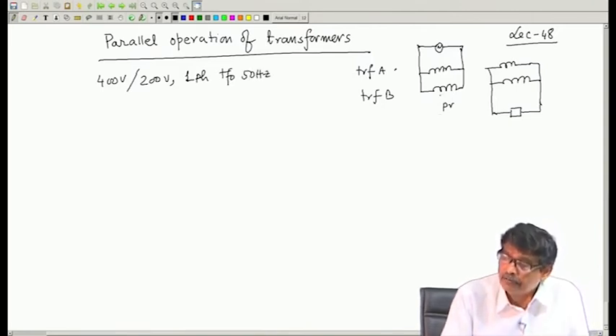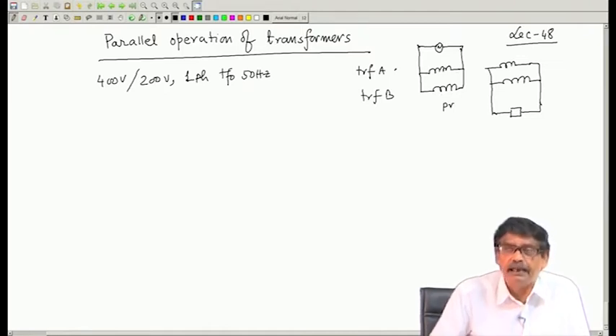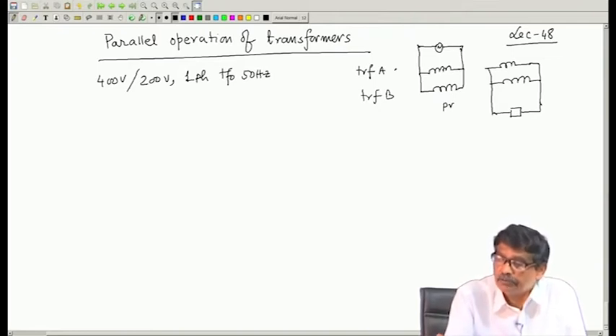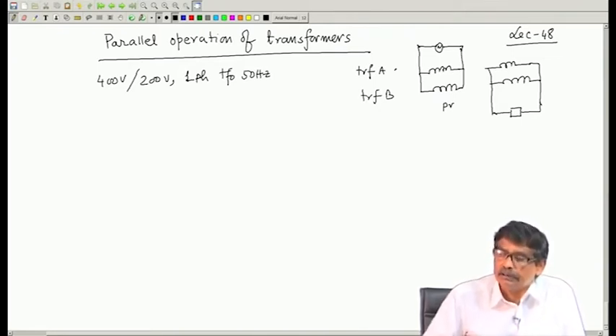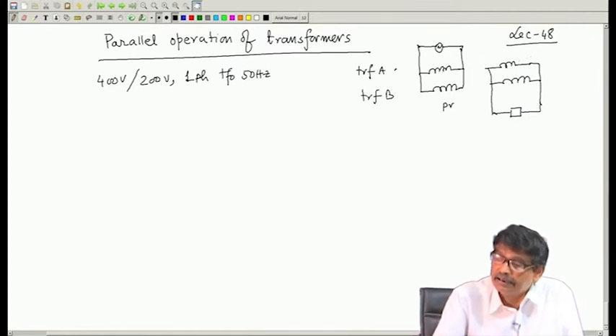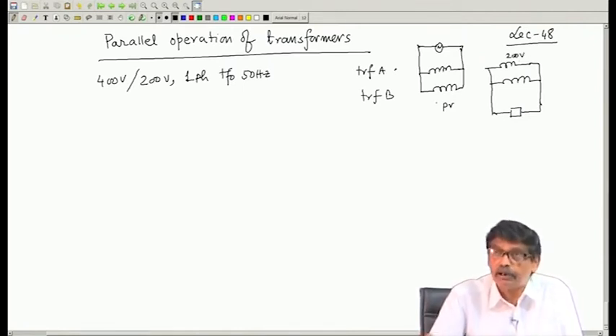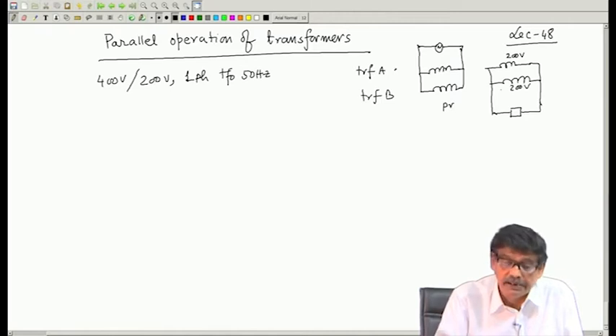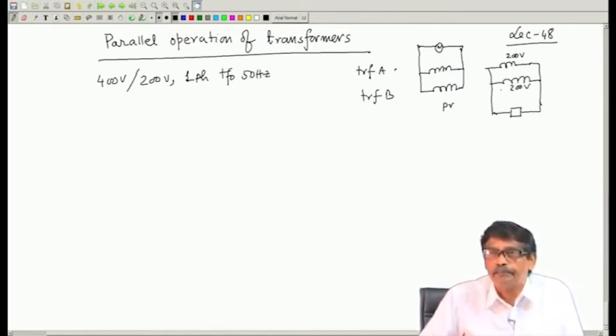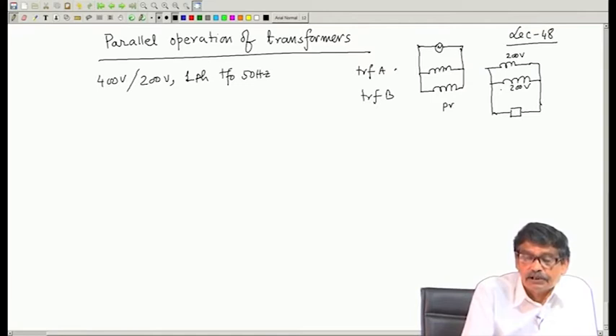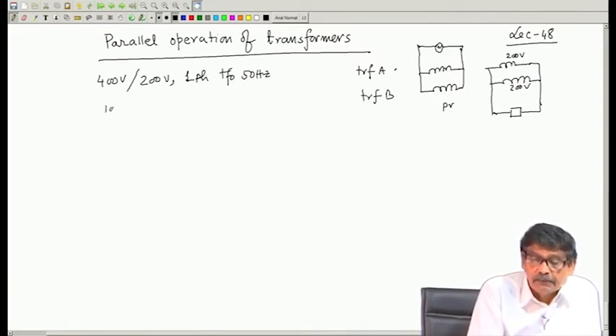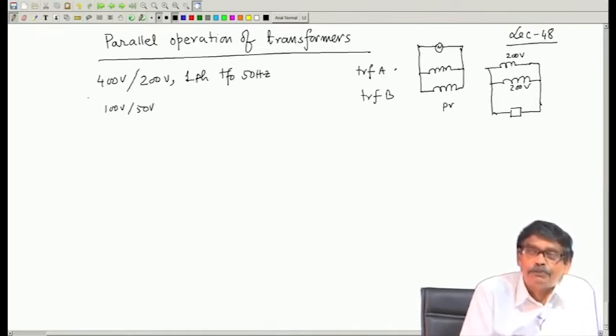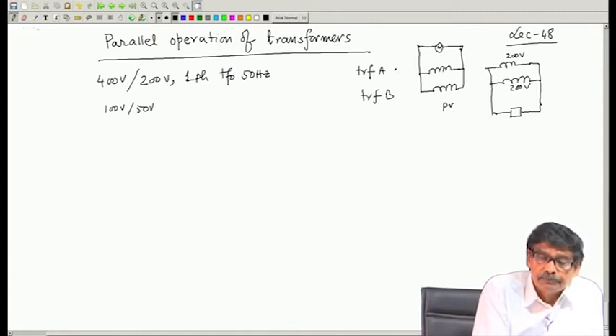Suppose on the 400 volt side I connect them in parallel, and it is absolutely logical. The rating of each one of them should be the rated voltage, so they are connected in parallel and supplied from the same source. Similarly, the LV side rating is 200 volt and we are going to connect them in parallel; voltage cannot be different. So, the voltage ratings of the primary and secondaries must be the same. For example, you will never think of connecting a transformer of rating 400 volt, 200 volt in parallel with 100 volt, 50 volt. These two cannot be paralleled for obvious reasons.